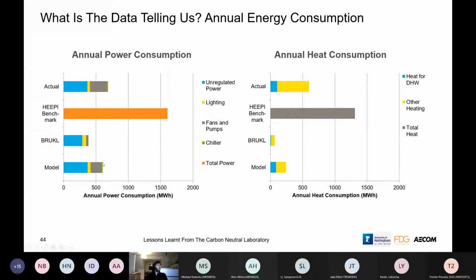The fans and pumps are using about twice what we targeted, which is not ideal. Again, that appears to be because our handling units aren't turning down properly overnight, which is something we're working on with the university. In terms of heat consumption, this is definitely too high - still a lot lower than the benchmark, and again the BRUKL just shows silly values, and it's a lot higher than our model. Again we think this is mainly due to the ventilation system not turning off at night properly.